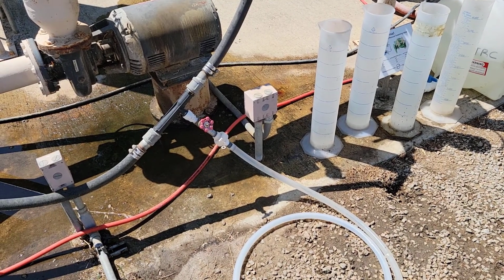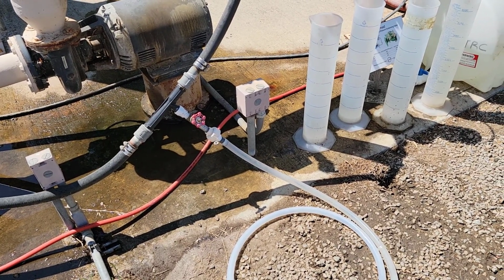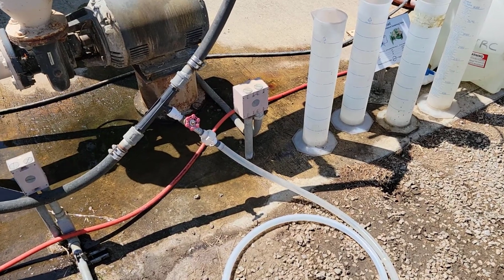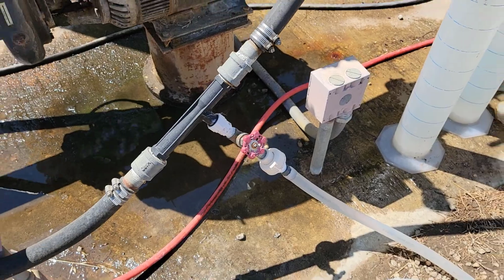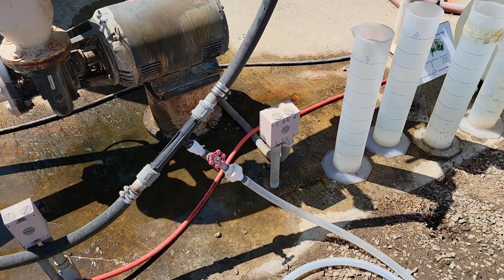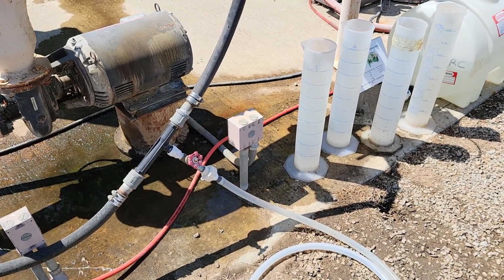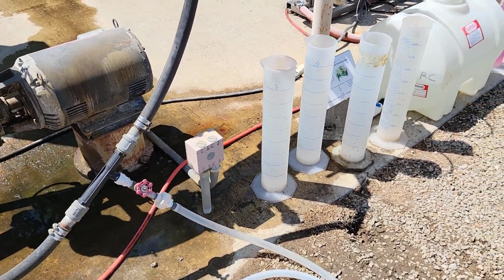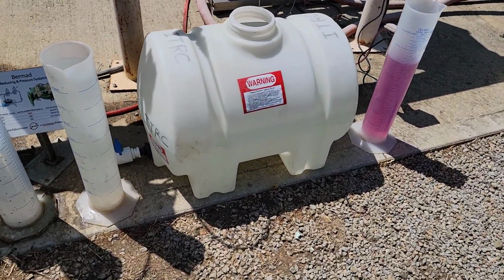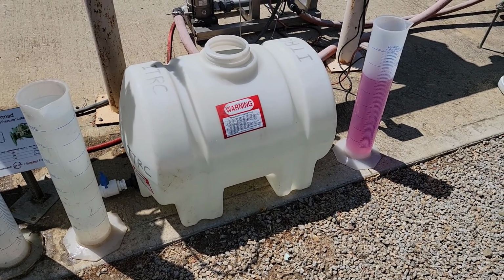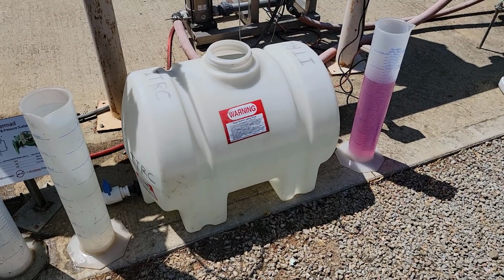All right, so we're going to start sucking in our acid for our test out here to determine the travel time. We're going to be using a Mazzei venturi, and we've got this valve dialed in here to give us about 3,000 milliliters a minute. Remember, we need to inject at a rate of about 100 milliliters a minute, but that's very hard to do with the Mazzei. So what we've got is a tank over here that's set up with the proper amount of water, and our 3,000 milliliters of acid is going to be mixed into that so we can inject at a higher flow rate, so that way we get accurate readings here.